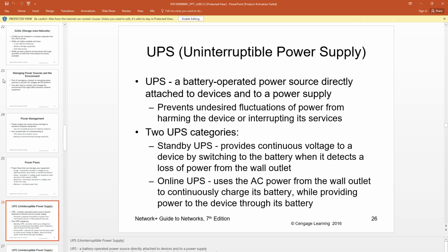But there really are two different kinds of backups. The UPSs that we've got here were about $150 apiece. They're not hugely expensive, but at your house you might say, I'm not going to spend $150 on one. There are some cheaper models, which are only what they call standby UPSs. They don't do anything until the power goes off. When the power goes off, they switch onto the battery, and you can run for 5 or 10 or 15 minutes on them. Those work very well, but they don't do anything about things like brownouts, where the voltage goes down, or dirty power.